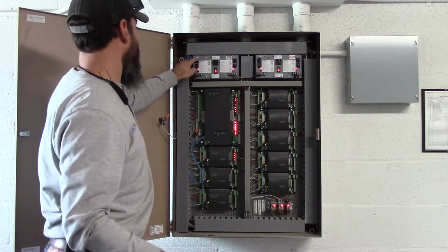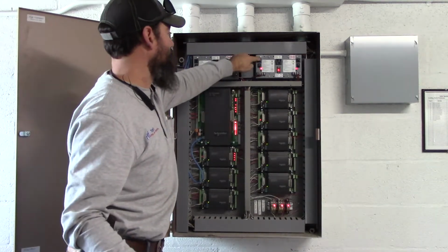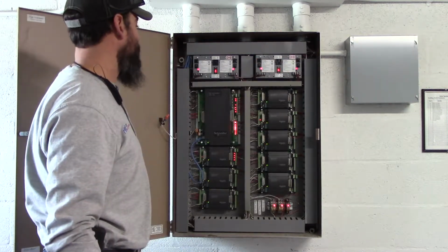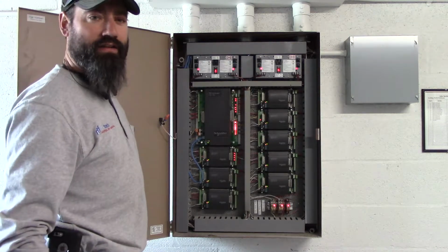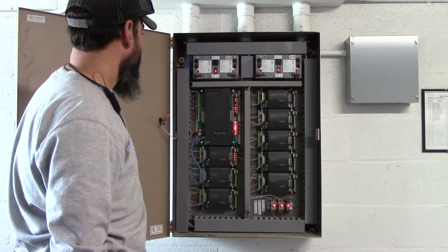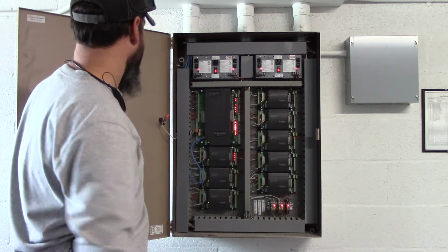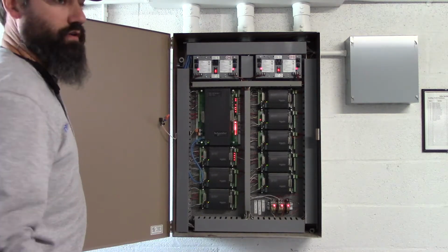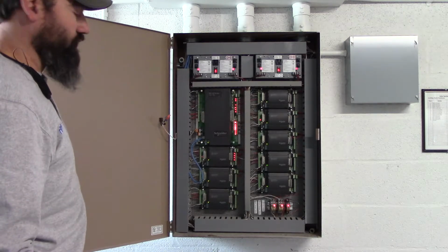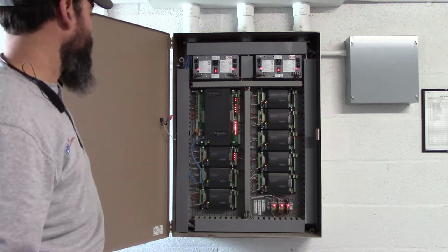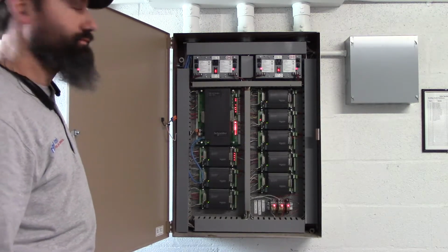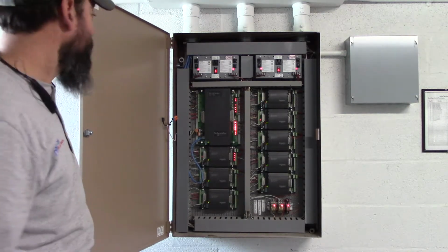If for some crazy reason you pull too many amps on a 24-volt circuit, you might trip a little breaker up here that might need to be reset. If you short something out by accident on the unit. But other than that, there's nothing really going on here. If you lose a unit on the control side of things, looking at the computer, you might come to this panel and make sure you got power. That's about all you can do.